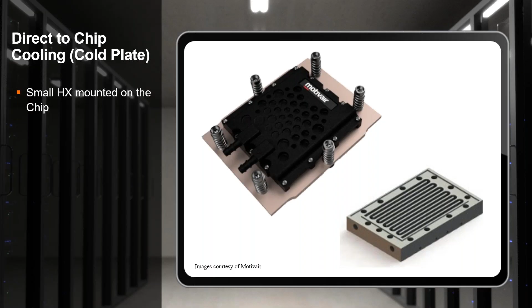So you can see these black rectangular pieces in here. That's your cold plate. There's 2 of them marked on this half server tray here, and we're bringing the fluid in. These are kind of piped in series, and it comes back out the other side. So an actual full board server might have 3, 4, 5 of these cold plates in there. Sometimes you'll have, as you see at the bottom here, multiple supplies and returns so that we get the cooling capacity that we need.